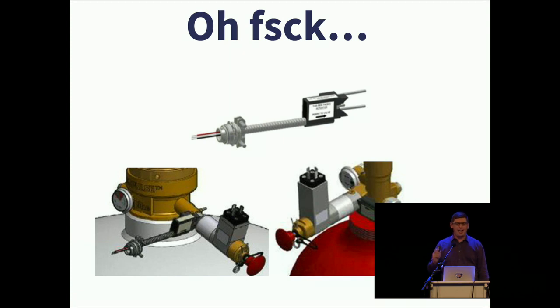We had a 1 in 1 million failure, according to Tyco. A firing mechanism on one of the big red FM200 cylinders failed, which activated the release of the FM200 chemical out of that cylinder. Not the end of the world, a bit pricey, but if it was just one cylinder, that would have been fine.